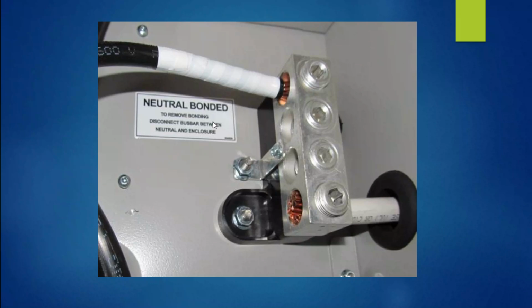and you're good to go. Here's another example of a strap that's utilized from the manufacturer. Again, no need to size this. I'm not sure how you would calculate it, because it's not necessary. The manufacturer does a lot of testing on this to make sure that this can handle the potential ground fault current imposed on it during a fault condition for the rating of this equipment. And so no need to reinvent the wheel when it comes to that.